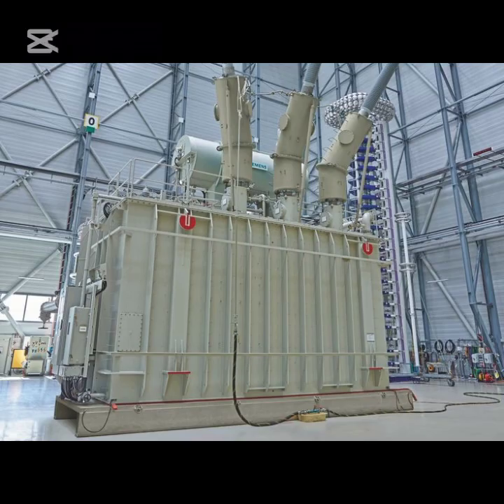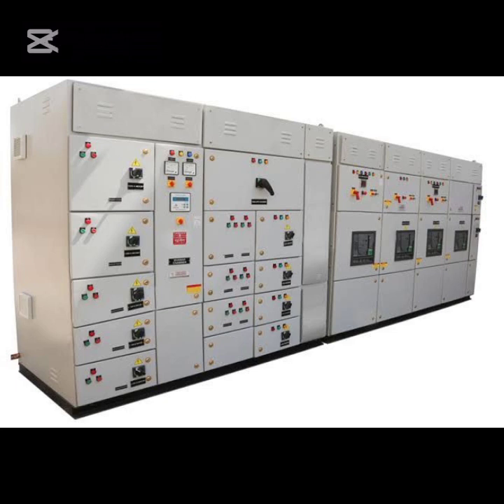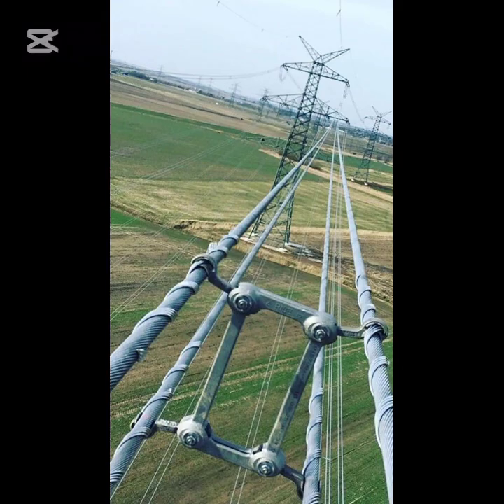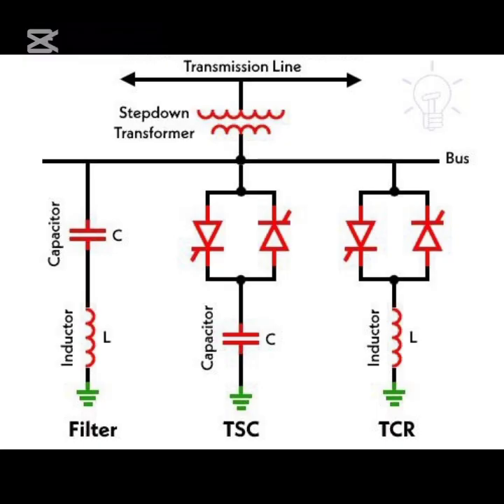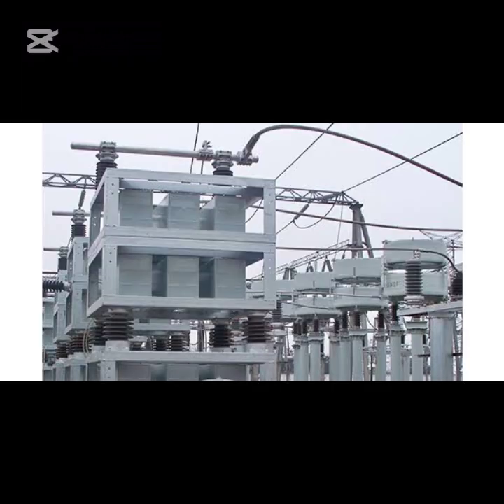Second, line length reduction: reducing the length of the transmission line can decrease the Ferranti effect. Third, voltage regulation: implementing voltage regulation devices such as tap-changing transformers can help maintain a stable voltage level. Fourth, power factor correction: improving the power factor of the system can reduce the Ferranti effect. Fifth, line design optimization: optimizing the design of the transmission line, such as using bundled conductors or adjusting the line geometry, can help minimize the Ferranti effect.